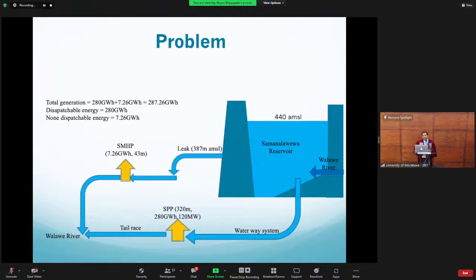Then we looked at the problem differently. So we brainstormed with my engineers, my colleagues, and looked at how we can do otherwise to stop this wastage of water. Then we considered this fact. The surface water level is about 440 meters above mean sea level. And the leak is at 387, about 53 meters below the surface level. Whereas the power plant, Samanalawewa power plant has a 320 meter head, that is 320 meters below 440 meter surface water level. So we thought, why not pump back the water 53 meters, and every cubic meter so pumped back can go through the power plant with a 320 meter head. So it looked to us sensible.